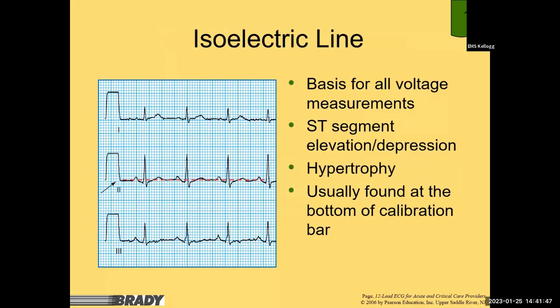The isoelectric line is the basis for all voltage measurements on a 12-lead. The machine fires up, activates, hits a flat line, then drops back down — where it drops to creates a box that almost looks like a capnography waveform, and that determines the beginning of the isoelectric line. It's usually found at the bottom of the calibration bar, and is generally accurate as long as leads are properly placed. ST elevation, depression, or ventricular hypertrophy can affect the isoelectric line.